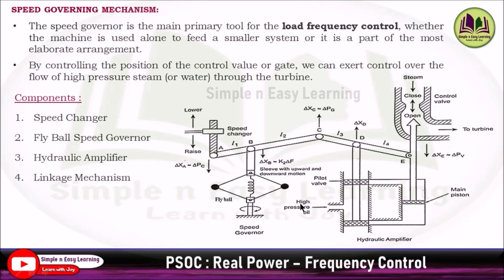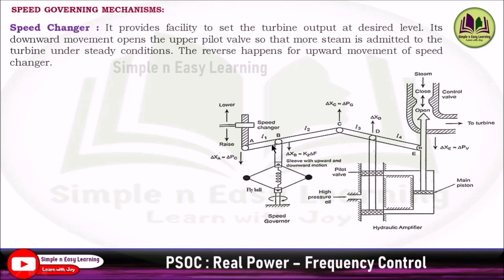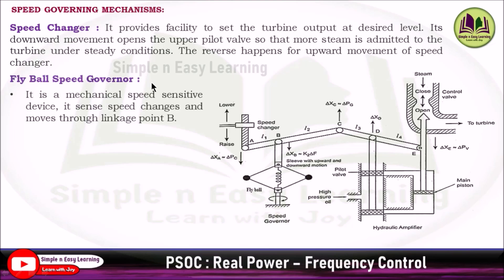The speed changer provides the facility to set up the turbine output at a desired level. Its downward movement opens the control valve so that more steam can be admitted to the turbine. Under steady state conditions, if the speed changer gives a raise command, the valve opens, more steam enters the turbine, and speed increases. In the upward movement, the control valve starts to close so that a minimum amount of steam enters the turbine, reducing the speed.